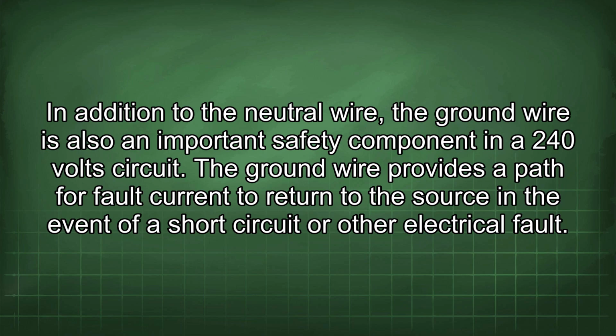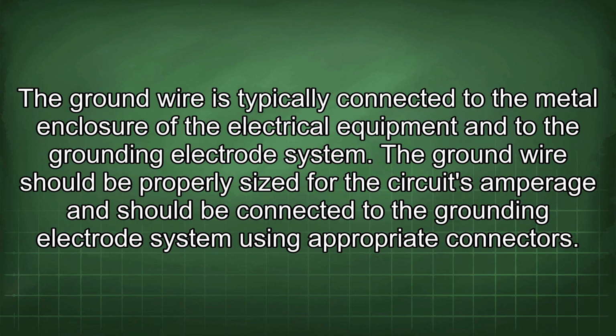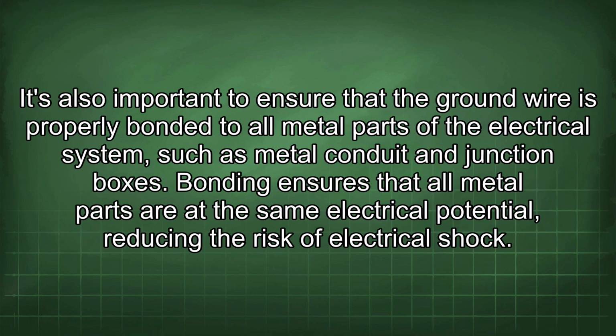In addition to the neutral wire, the ground wire is also an important safety component in a 240-volt circuit. The ground wire provides a path for fault current to return to the source in the event of a short circuit or other electrical fault. The ground wire is typically connected to the metal enclosure of the electrical equipment and to the grounding electrode system. The ground wire should be properly sized for the circuit's amperage and should be connected to the grounding electrode system using appropriate connectors. It's also important to ensure that the ground wire is properly bonded to all metal parts of the electrical system, such as metal conduit and junction boxes. Bonding ensures that all metal parts are at the same electrical potential, reducing the risk of electrical shock.